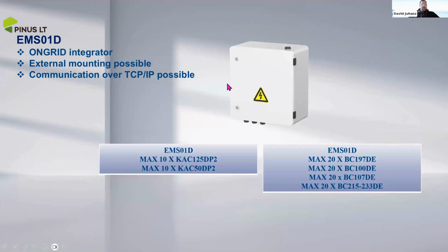This is the picture of the EMS01D on-grid system integrator equipment. External mounting is possible, and the communication with the battery cabinets is over TCP/IP. The limitation is a maximum of 10 pieces with the new inverters, and the old ones have a maximum of 20 pieces for the inverters.